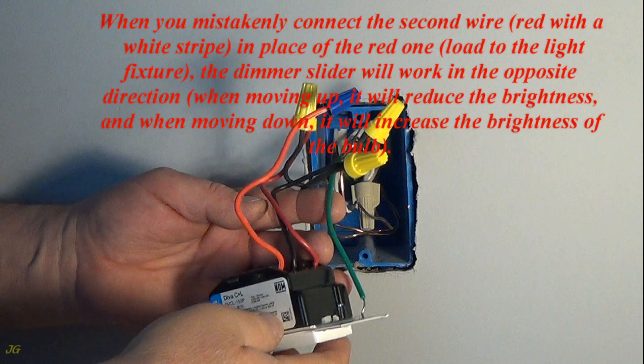When you mistakenly connect the second wire (red with a white stripe) in place of the red one (load to the light fixture), the dimmer slider will work in the opposite direction. When moving up, it will reduce the brightness, and when moving down, it will increase the brightness of the bulb.